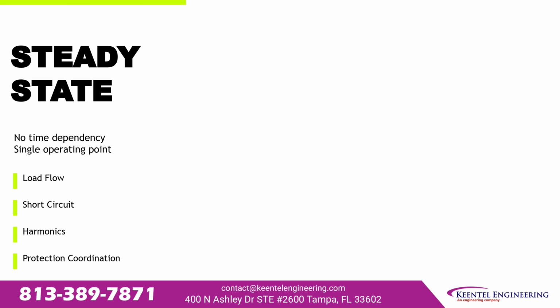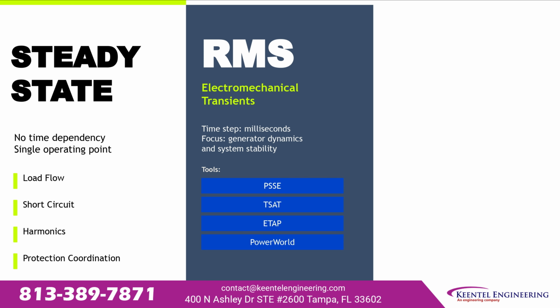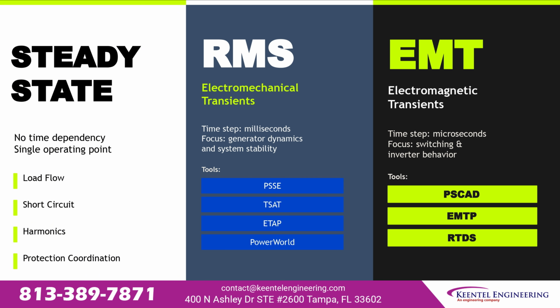Power system simulation spans three distinct domains. Steady state: no time dependency, single operating point. This covers load flow, short circuit, harmonics, and protection coordination. RMS, electromechanical transients: time step in milliseconds, focused on generator dynamics and system stability. Tools here include PSS/E, TSAT, ETAP, and PowerWorld. EMT, electromagnetic transients: time step in microseconds, focused on switching behavior and inverter dynamics. Tools here are PSCAD, EMTP, and RTDS. Each domain answers different questions. Confusing them produces results that look valid and are not.